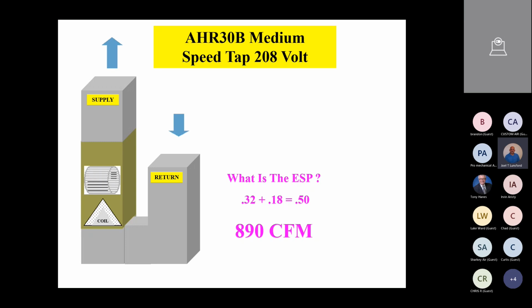And again, this is kind of generalized. I don't normally like talking about generalizing or rules of thumb, because every manufacturer is different. But typically, most manufacturers, residential application, if the coil is clean and you've got condensate running down the coil, you can figure they have a static pressure drop across the coil of about 0.2. Does that make sense? So in other words, if I poke a hole in the cabinet above the coil, and I read a 0.2, then add another 0.2 for the coil for a total of 0.4. You with me? Yeah, that makes sense.